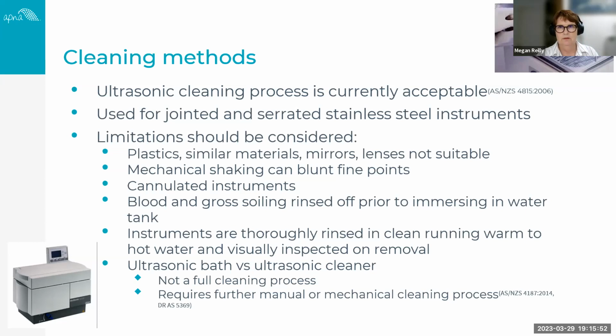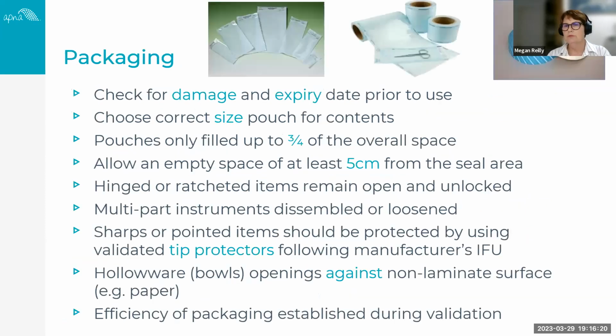Okay. And I've just popped that little picture up there in the vain hope that your ultrasonic cleaner, when you place your instruments into the basket, will look like that. It will be a single layer of instruments, not a whole load of instruments jammed in on top of one another, because that won't actually produce good cleaning of those instruments, which is what we want. So our packaging is also a really important part of the process.